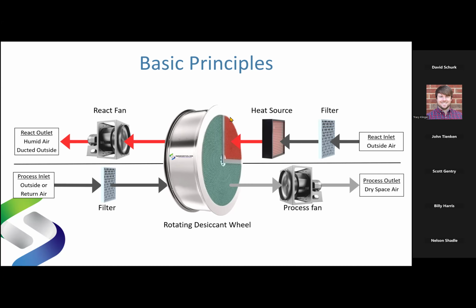And as this air that has been heated comes in contact with the substrate material, it heats the desiccant, heats the wheel a little bit, and it increases the vapor pressure of the moisture in the desiccant to be above the vapor pressure of the air in the reactivation airstream. And guess what? It desorbs. It spits loose the water molecules that were in that wheel, it dries the wheel out, and I then get rid of them outdoors. And as long as the wheel is turning, and as long as the fans are moving, and as long as this heater is working, I have dehumidification, right? I'm taking low vapor pressure silica gel, adsorbing moisture, rotating it into an opposing airstream, increasing its vapor pressure, desorbing the moisture, and the world is a beautiful place.